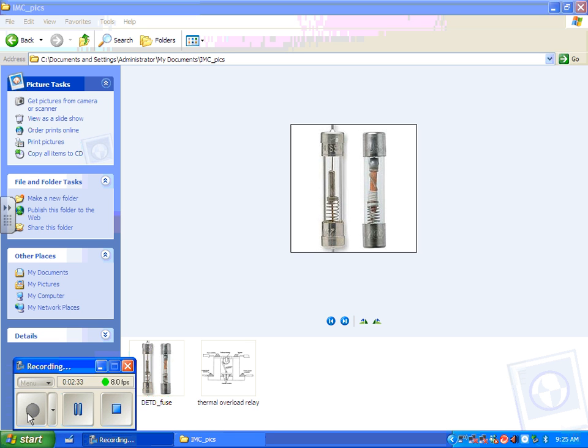A dual element time delay fuse uses two parts. One part melts on extreme overloads, and that's the branch circuit protection. Then there's a solder piece and a spring that protects the motor on the motor overload portion. Generally speaking, we use dual element time delay fuses in motor control anyway, because we want that inrush current to happen for a couple of seconds. Sometimes we need to let 6 to 8 times the full load amperage flow to the motor so that it will start. If it won't start, it's not going to do you any good, right? So you've got to allow that inrush to happen to get things going.